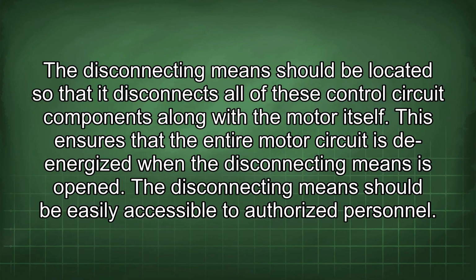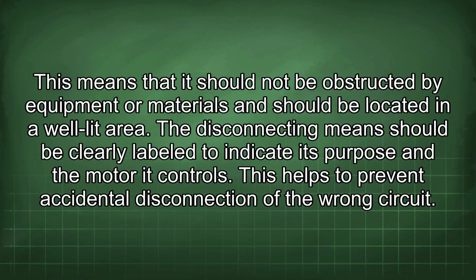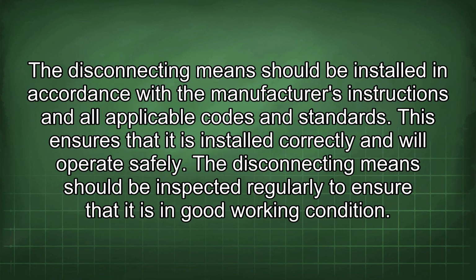The disconnecting means should be easily accessible to authorized personnel. This means that it should not be obstructed by equipment or materials and should be located in a well-lit area. The disconnecting means should be clearly labeled to indicate its purpose and the motor it controls. This helps to prevent accidental disconnection of the wrong circuit. The disconnecting means should be installed in accordance with the manufacturer's instructions and all applicable codes and standards. This ensures that it is installed correctly and will operate safely.